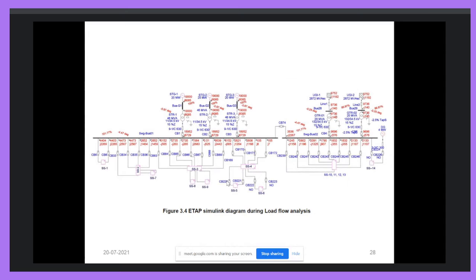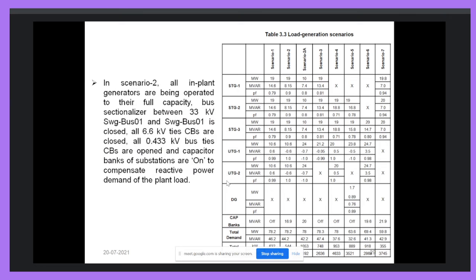In this diagram you can see the load flow results. Consider that the generators are supplying 19 megawatt generation, contributing 19 megawatt per generator. There are 3 generators. The rest of the power is drawn from the utility, and you can see the utility grid also supplying power. For the different operating scenarios and different combinations of load and generation, this table presents the contribution of power of the in-plant generators and the utility grid. For the different operating scenarios, the generation is different, the power drawn from the utility grid is different, and the losses of the system will be different. We have analyzed the system for different load demands and prepared the database for training and testing purposes of the ANN.